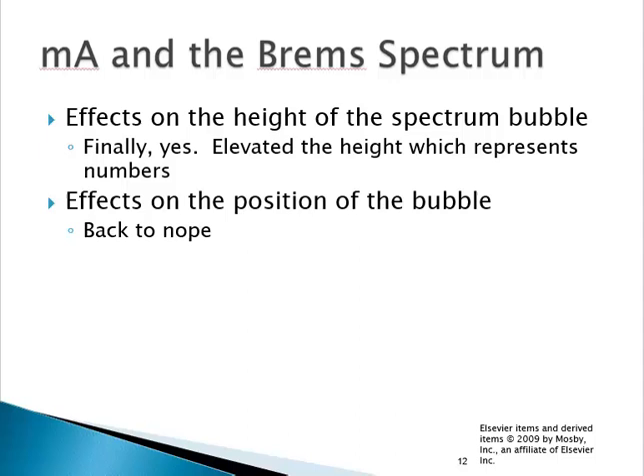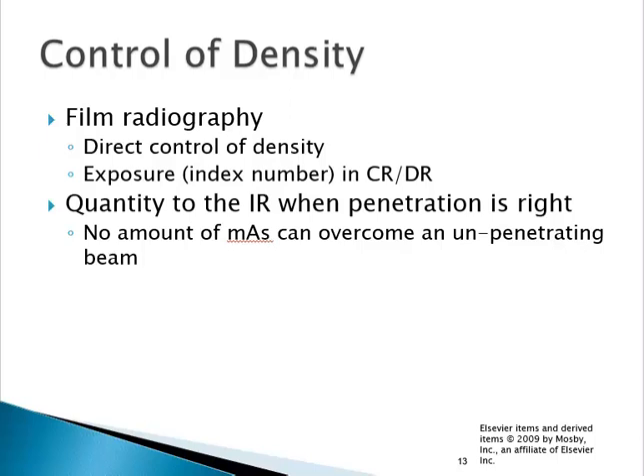Control of density: remember that density equals exposure. In film radiography there was a direct correlation between MAS and density. Whenever we increased KVP, we did increase density provided we didn't change our MAS, but we altered the imaging characteristics of the x-ray beam — a visible change in contrast. So mAs only controlled density, kVp controlled density and contrast. mAs was our direct control of density.